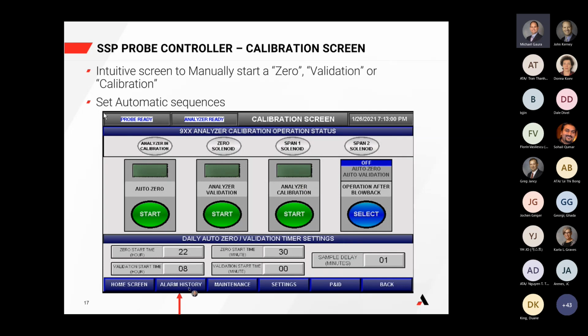So I just wanted to add in here quickly, this is not a replacement for your typically mandated DAS controlled system, where your calibrations are set at a specific frequency. This is not a replacement for that. This is specifically for the SSP probe, but it does allow you some flexibility to do things as part of the testing and maintenance procedure. You would not typically run your normal analyzer validation through the SSP probe controller. That would be part of whatever your DAS system is.